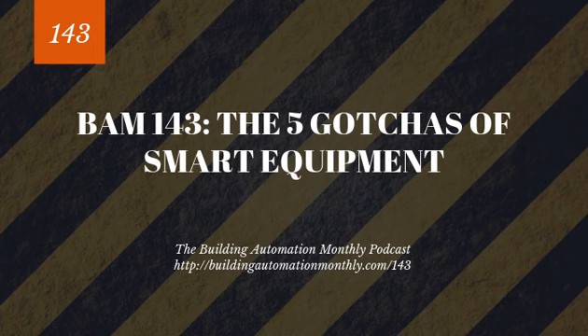Maybe you could argue with energy recovery wheel systems, where that's a specific system controller and then you've got a free programmable controller for the rest of the unit. But in reality, the argument for segmenting a system, I mean, it's just fix the sequence. Oftentimes, the reason folks do system segmentation is because the sequence cannot be executed any other way. So that is trying to fix an issue with the sequence by hodgepodging the equipment, or you could argue fixing a problem of the equipment to achieve a perfectly good sequence, depending on how you look at it. The point here, though, is to be aware of that, especially if you're a design engineer or an owner or a service person. Be very aware of segmented systems.